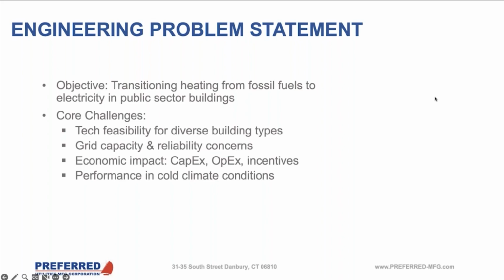That has to do with your air source heat pumps - their efficiency starts to drop off as ambient temperature drops. You also start to lose capacity. So as your efficiency drops off, you're essentially using more electricity to make the same amount of heat.